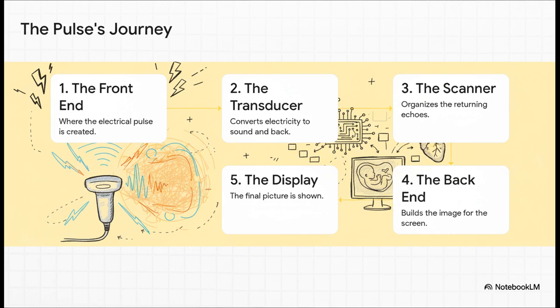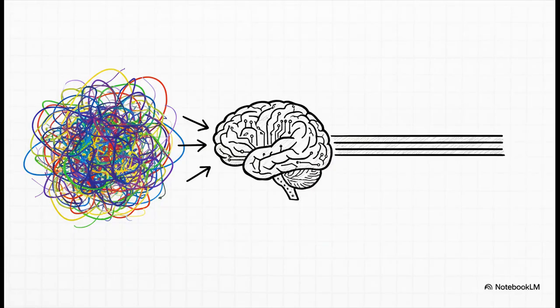Back to our map, that signal has now traveled deeper into the machine, entering the section we call the scanner. This is where the heavy lifting and complex processing really begins, starting with a piece of hardware called the beamformer. The beamformer is amazing. Think of it like the conductor of an orchestra. Inside that transducer are thousands of tiny crystals, and the beamformer tells each one precisely when to fire, down to the nanosecond. By organizing them perfectly, it gets them all to sing in harmony, creating a single, focused beam of sound. It pulls a clean, coherent signal out of a sea of potential noise.